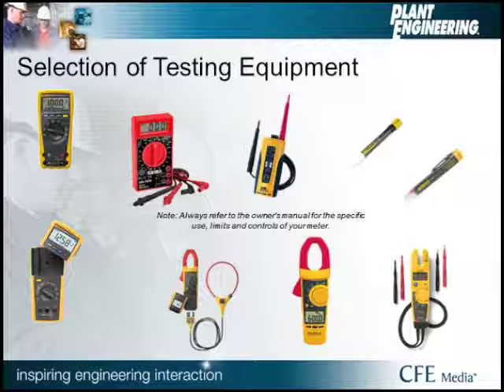Most voltage detectors have a range of 50 to 100 volt detection. Well, they go as high as 600, but they don't sense a voltage until 50 volts. When we do lockout tagout, we're looking for 0. The other problem with voltage detectors is they can't measure through insulated cable, and they can be canceled out if they're between 2 fields. So they're not used in lockout tagout. And remember, always refer to your owner's manual for the specific use limits and the controls of your meter.